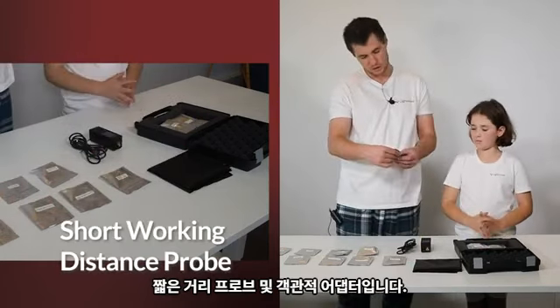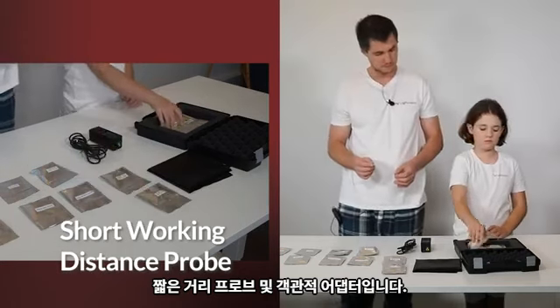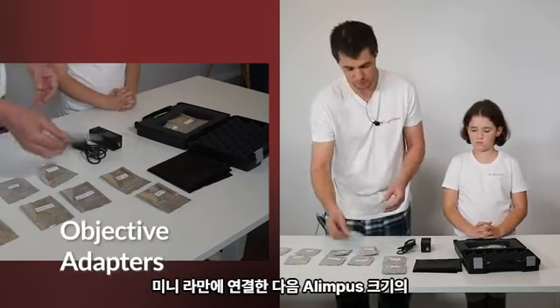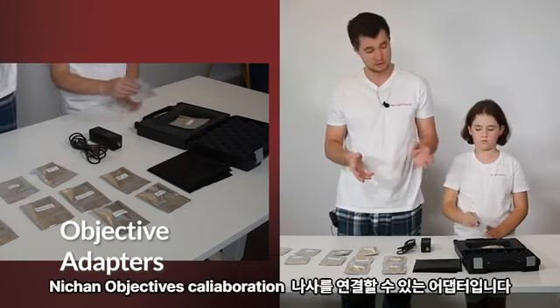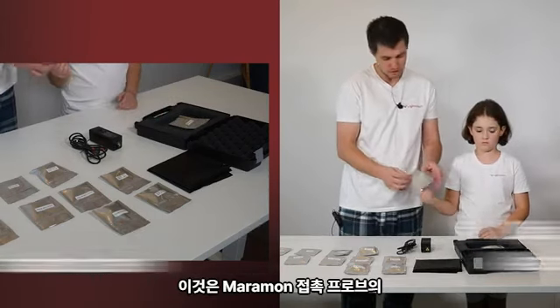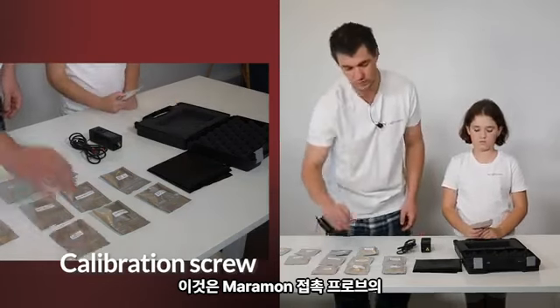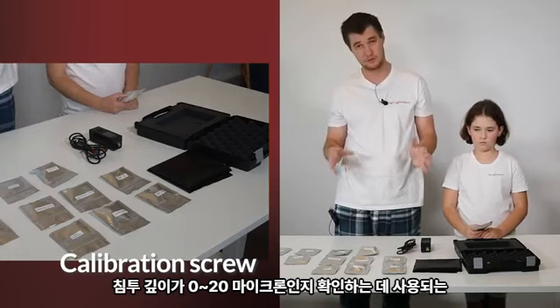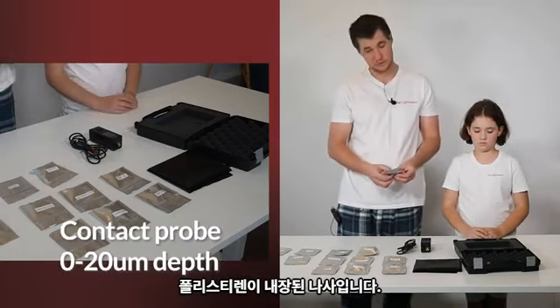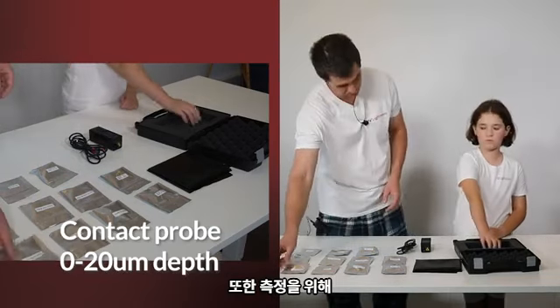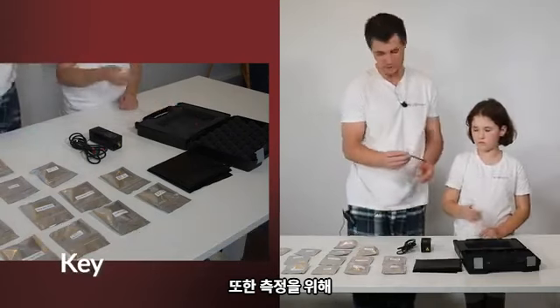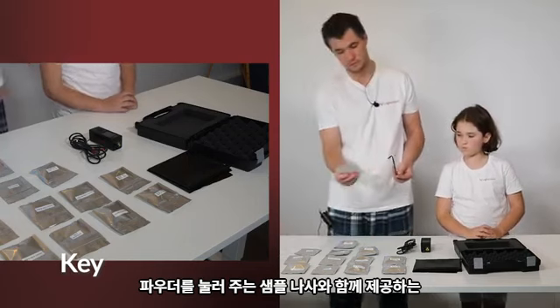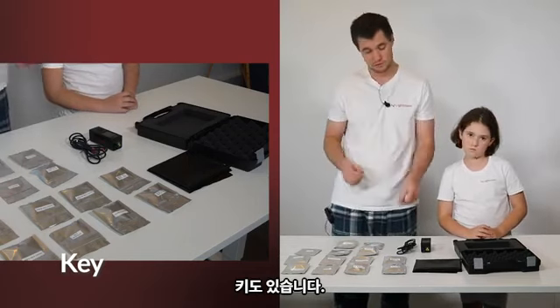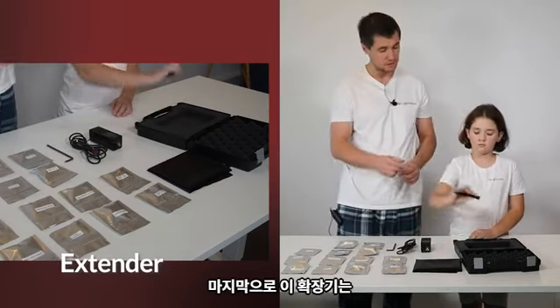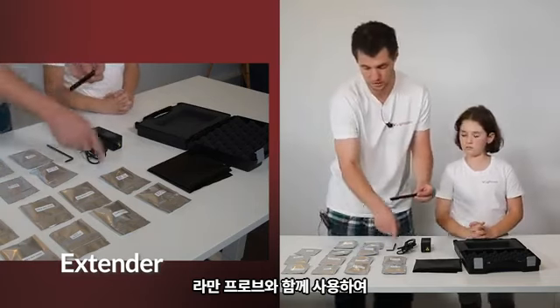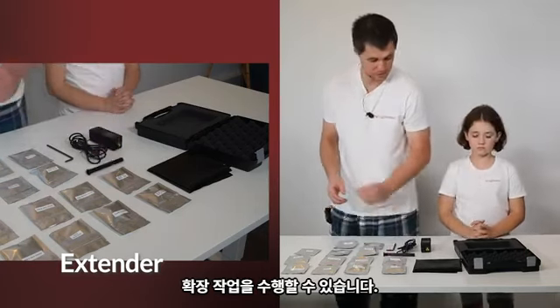Yes. Short working distance probe, and objective adapters. Those are the adapters which you can attach to mini-Raman and then connect Olympus, Zeiss, Nikon objectives. Calibration screw. This is a screw with inbuilt polystyrene which you will use to check the performance of mini-Raman. Contact probe for penetration depth 0 to 20 microns. Yes, and we also have the key. This key we supply together with sample screws, which you will press your powder to do the measurements. And finally, this is an extender which you can use with any of our Raman probes to have extended operation.